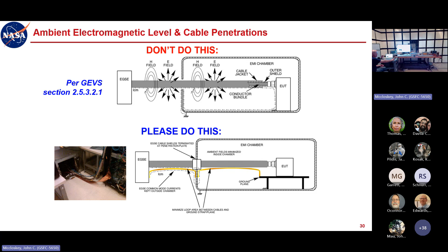A couple of suggested ways to do that. The preferred method is just put a connector break. All right, so you have your feed through plate at the wall. There, lost my cursor. There it is again. So you have the feed through plate at the wall, and that's conductive. Otherwise, it's doing you no good. And you terminate the shield's 360-degree coverage and terminate it to the back shell on both sides. Right, this is the preferred method.